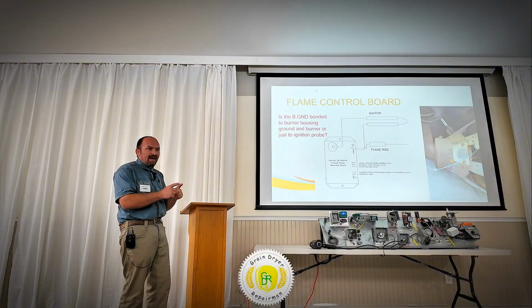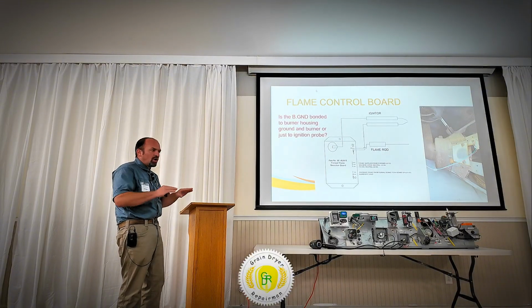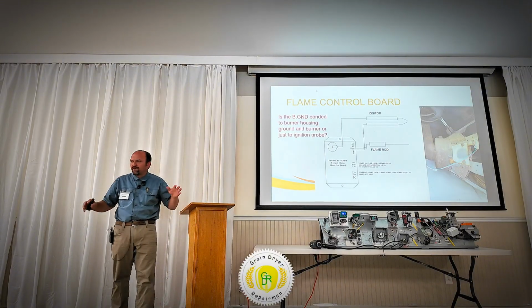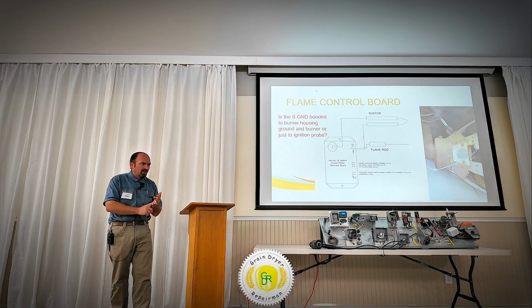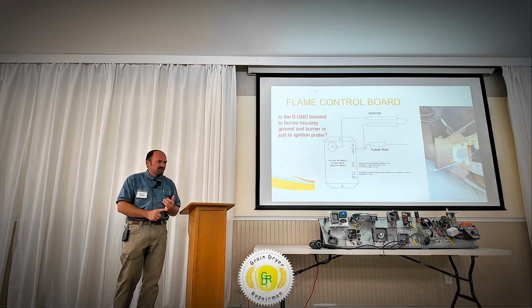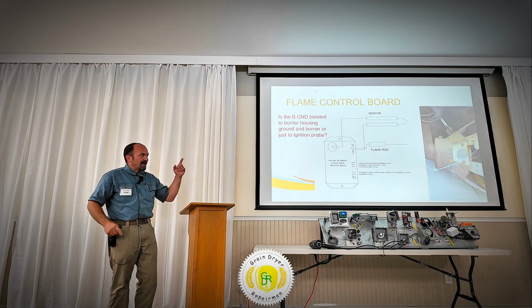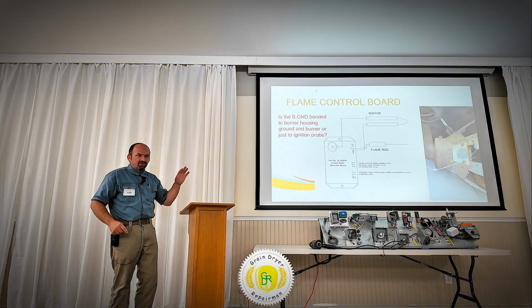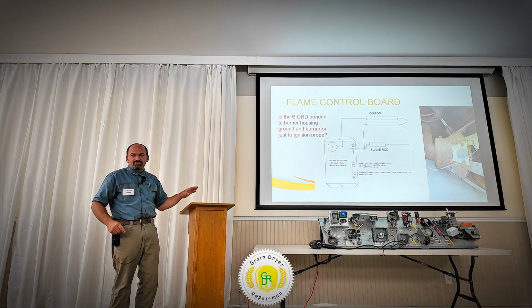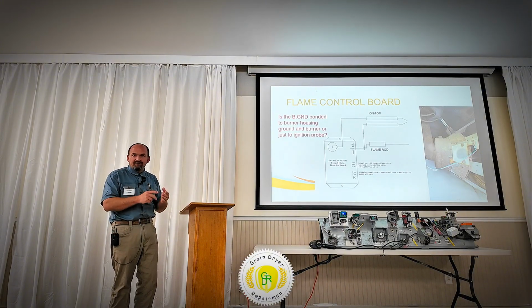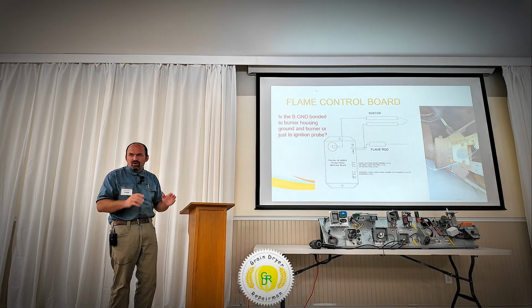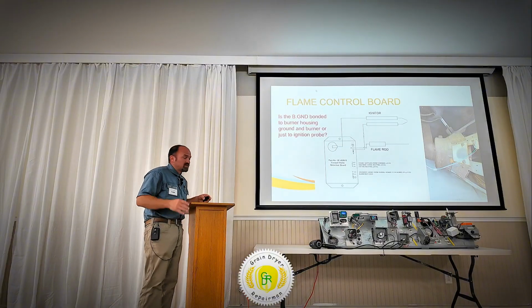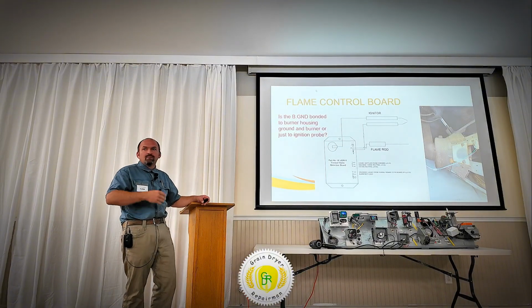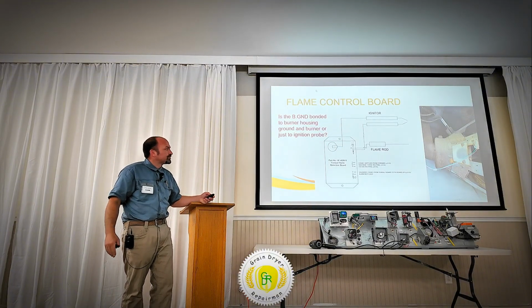The ignition gap is very important across all dryers. I don't care what dryer you're working with. Your ignition gap, your spark plug gap, should be an 1/8 inch. On these, you can have up to a 3/16. Once you hit a 1/4 inch, you're going to start running into trouble. You must have a 1/8 inch gap, can be up to 3/16, but no larger. Somewhere within that 1/16 inch is where you're going to get the hottest spark, but yet not have problems.